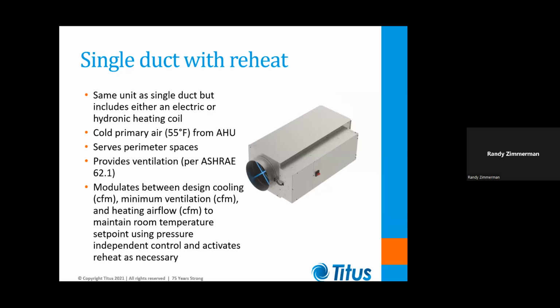Now, when we put reheat on a single duct box, it's important to know that we have to have at least 3 different flow rates there. We still have our cooling design airflow. We still have our minimum ventilation airflow, but then it's nice to have a heating flow rate so that the box can move, let's say, from 100% cooling down to maybe 15 or 20% ventilation, then maybe open back up to 50% to get some more air through the coil for doing our heating of the space. And of course, that would be typically used for either constant volume rooms or perimeter rooms where we're doing VAV and we have to counter the loads from glass and exterior walls.